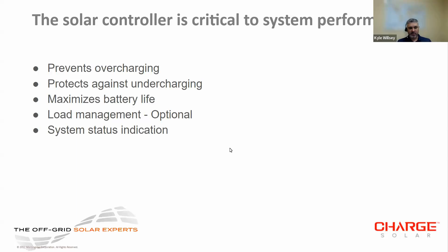A big part of that is load management. LVD is typically what comes to mind when we talk about managing primarily DC loads in an off-grid system. That's built into almost everything we do, as well as managing the charge into the battery. It's just as important to manage the outflow and have that tuned correctly to avoid over discharge or discharge in suboptimal temperature ranges. Being the central part of the system, the charge controller gives the user or operator an indication of the health of that system, the status of the solar inputs, any other inputs that might be there, and the battery itself.